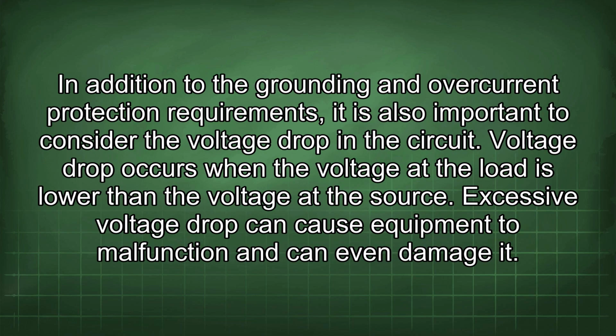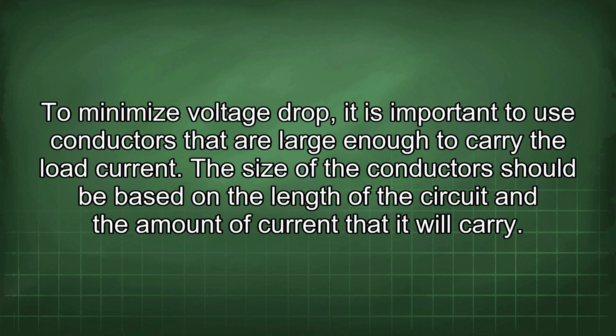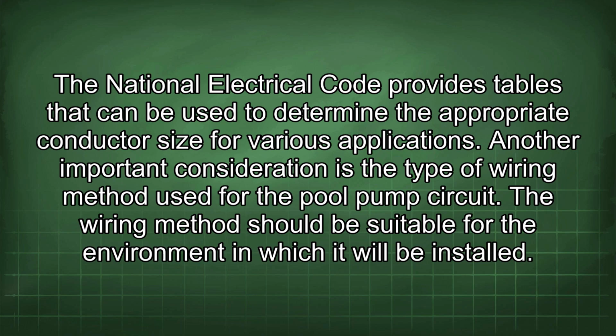In addition to the grounding and overcurrent protection requirements, it is also important to consider the voltage drop in the circuit. Voltage drop occurs when the voltage at the load is lower than the voltage at the source. Excessive voltage drop can cause equipment to malfunction and can even damage it. To minimize voltage drop, it is important to use conductors that are large enough to carry the load current. The size of the conductor should be based on the length of the circuit and the amount of current that it will carry. The National Electrical Code provides tables that can be used to determine the appropriate conductor size for various applications.